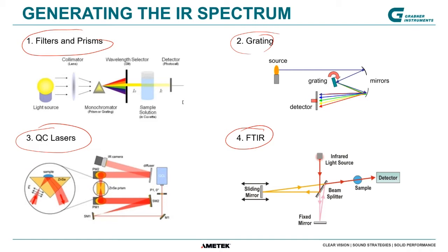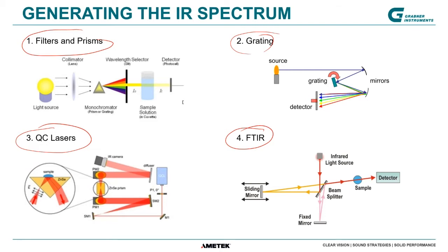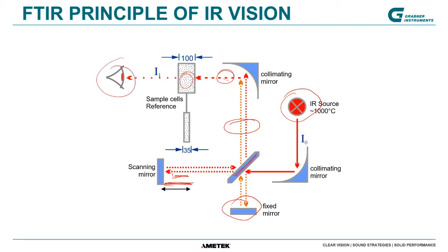The interferogram is then transformed to an absorption spectrum by means of a Fourier transformation. This is basically the setup of the Michelson interferometer in the FTIR system we are using. You have a light source with incoming radiation, then a beam splitter — the heart of the interferometer — which reflects one part of the light to a scanning mirror moving back and forth, and the other part to a fixed mirror. Both beams combine when they return, and depending on the phase shift introduced by the scanning mirror, you get a different radiation intensity. The sample also absorbs particular portions, a detector measures the intensity, and the intensity is plotted versus the scanning mirror distance, producing an interferogram.